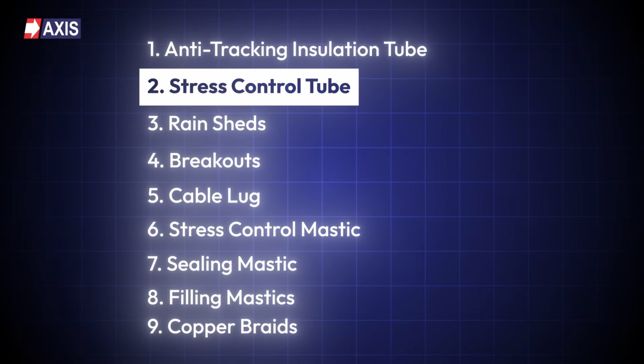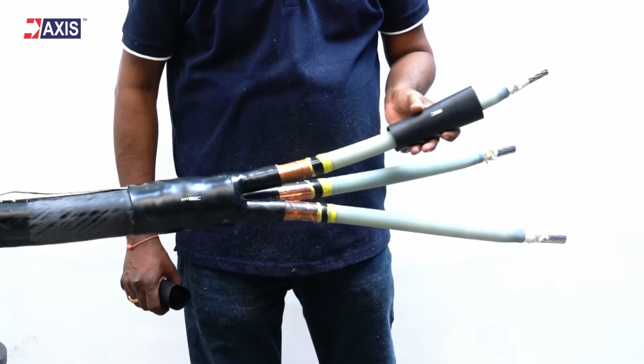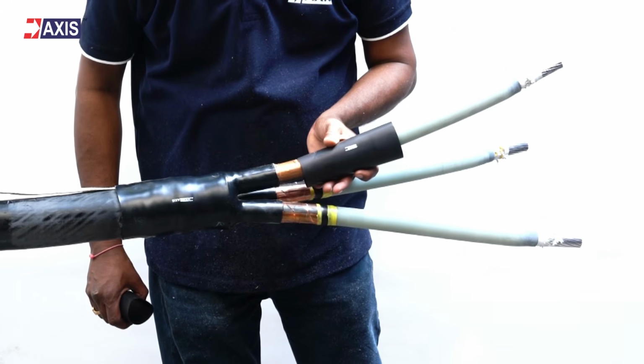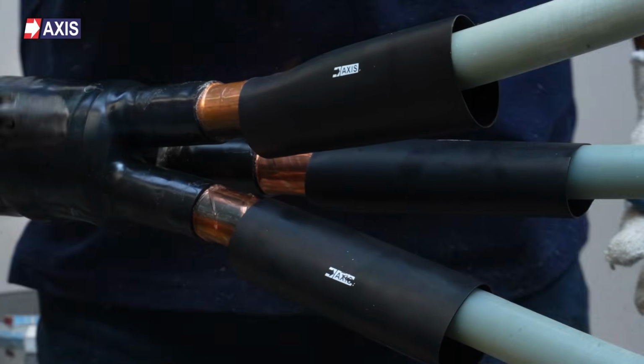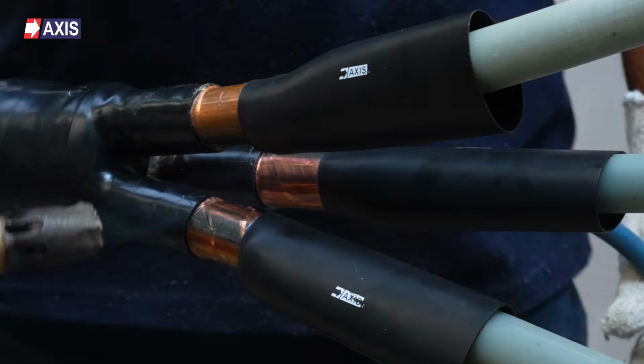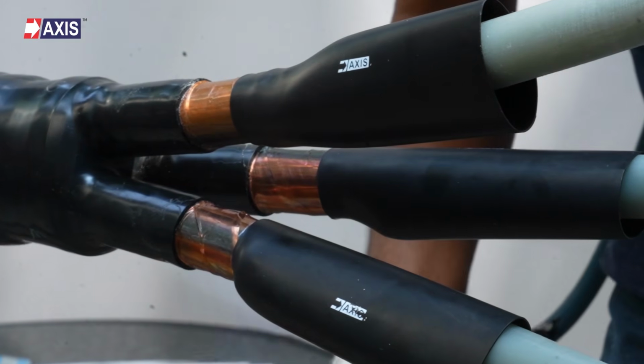The second component is a stress control tube. Made from a specially formulated cross-linked polyolefin with stress controlling properties, its role is to manage and redistribute electrical stress. This is especially important at the semiconductive screen cut area of the cable, where stress concentration is the highest. When heated, the tube shrinks over the insulation screen transition and smooths the electrical field. This reduces the risk of partial discharge and premature insulation failure, ensuring long-term reliability of the termination.